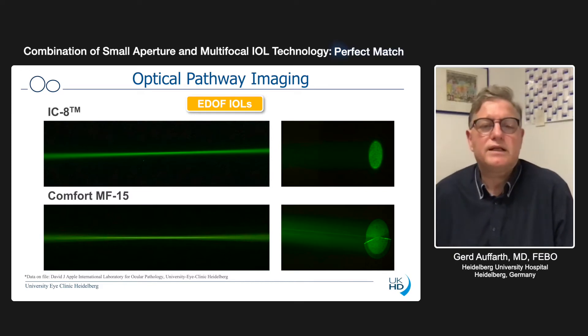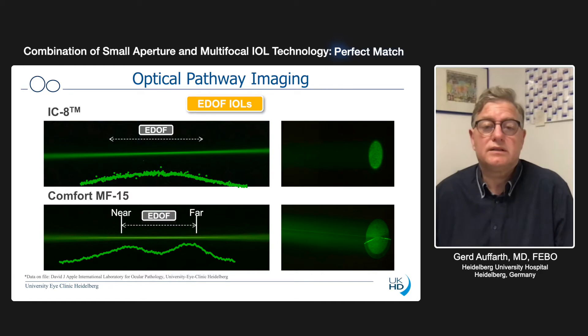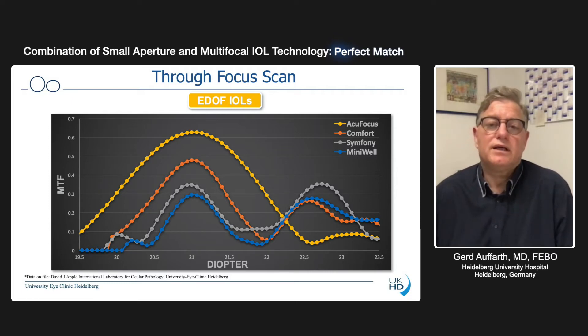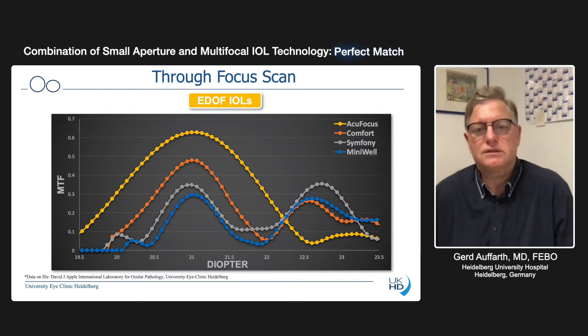The Comfort lens from Oculentis — I mention it because it's used widely in Europe and Asia — is nothing other than a bifocal lens with a near and far focus, with the near focus at 1.5 diopters, so around 70 centimeters. If you look on the optical bench at the through-focus curve, you see the yellow dotted line which is the AcuFocus line. It has the best and highest MTF, and also the broadest compared to all other IOLs on the market. It gives you almost 2.5 diopters of depth of focus, and it's one big peak — not two peaks as other EDOF lenses have.